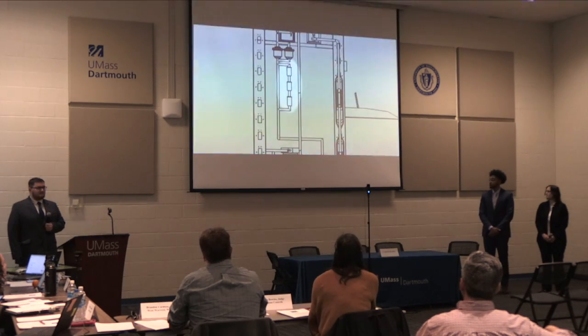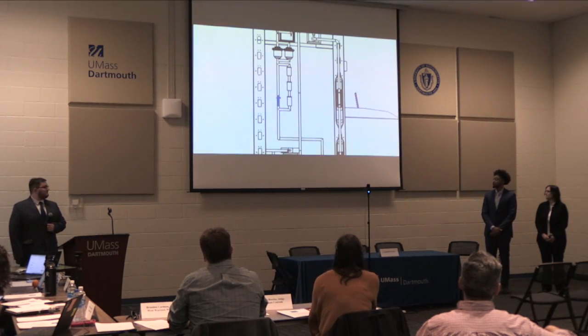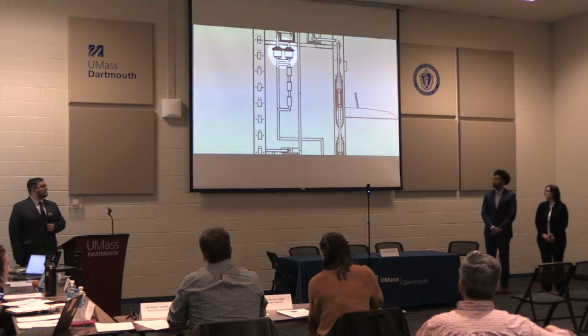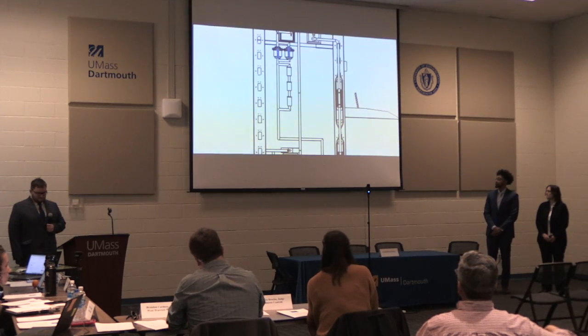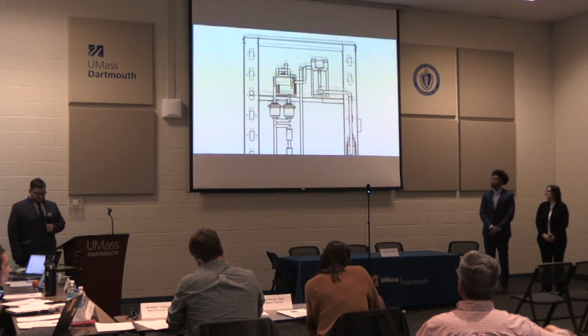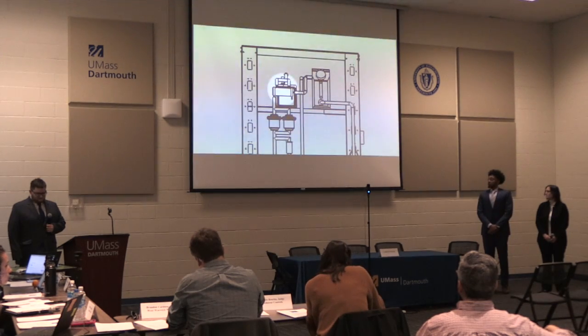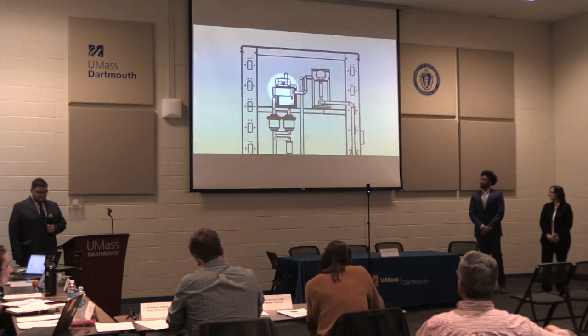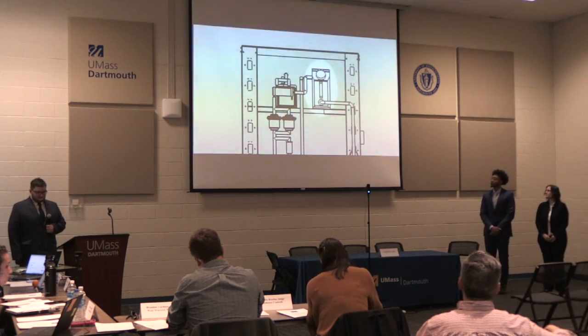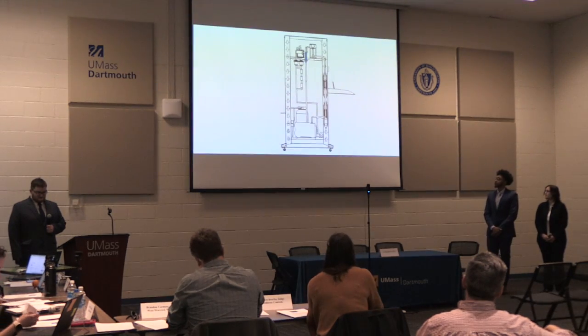Water then passes through the coarse membrane filtration line. This line can also be bypassed once water has been filtered repeatedly. Above this, our twin ultrafine polishing filters remove any remaining particles. A degasser module is used to remove any visible gas bubbles. This water is then channeled into a head tank, where an overflow line is used to maintain a constant height of water.